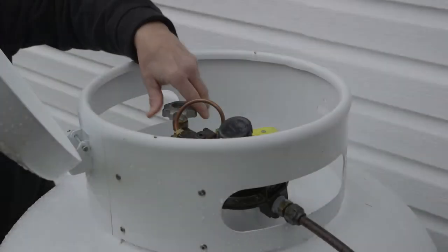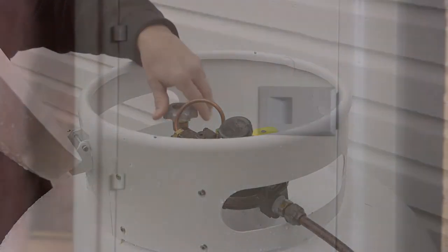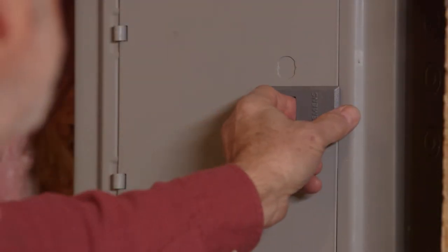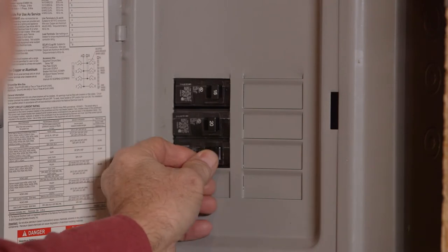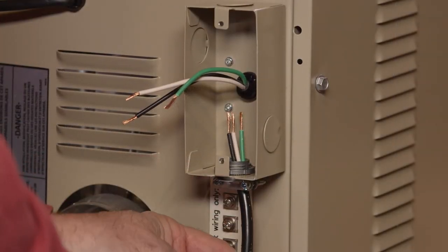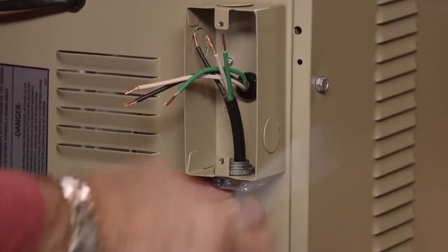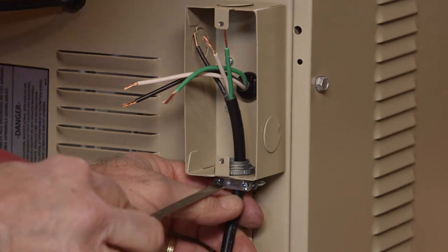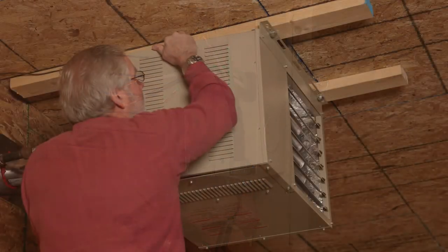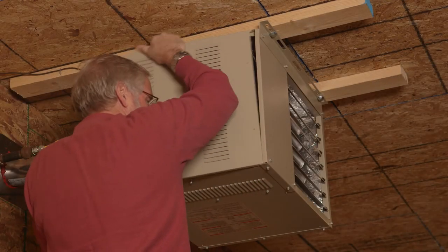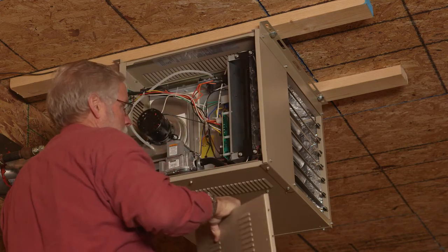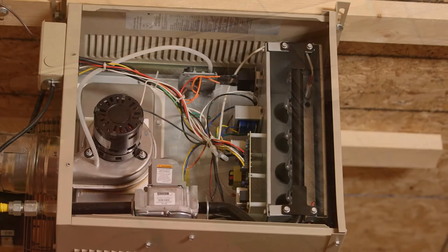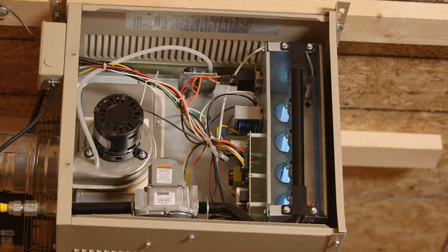Be sure to shut off all gas and electrical power of the unit before performing any maintenance or service. Any replacement wiring must have a temperature rating of at least 105 degrees Celsius. Before each heating season, inspect burners for any deposits or blockage. During heating season, periodically inspect burner flames for proper appearance.